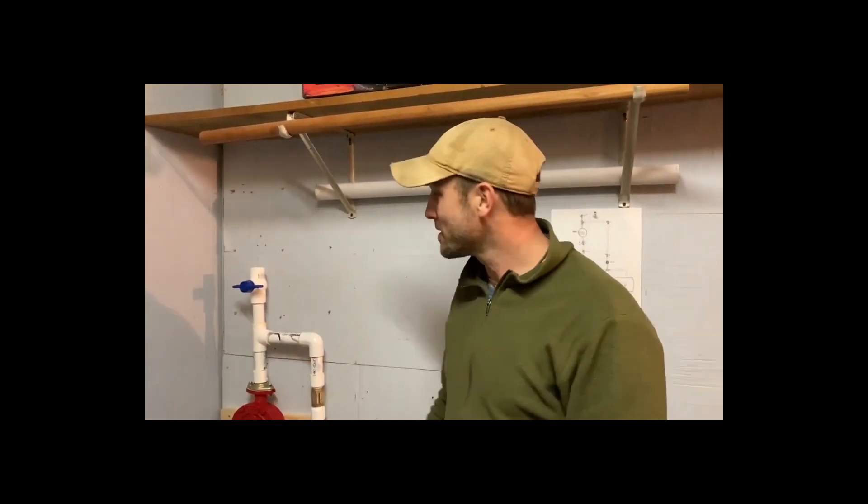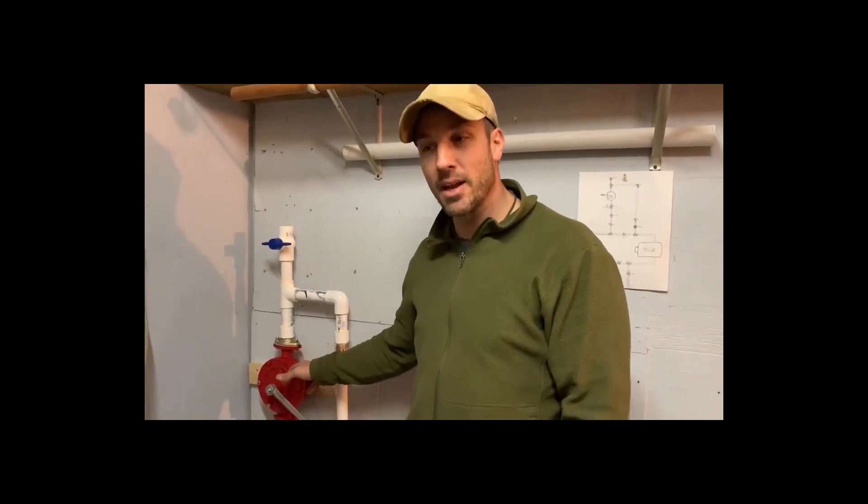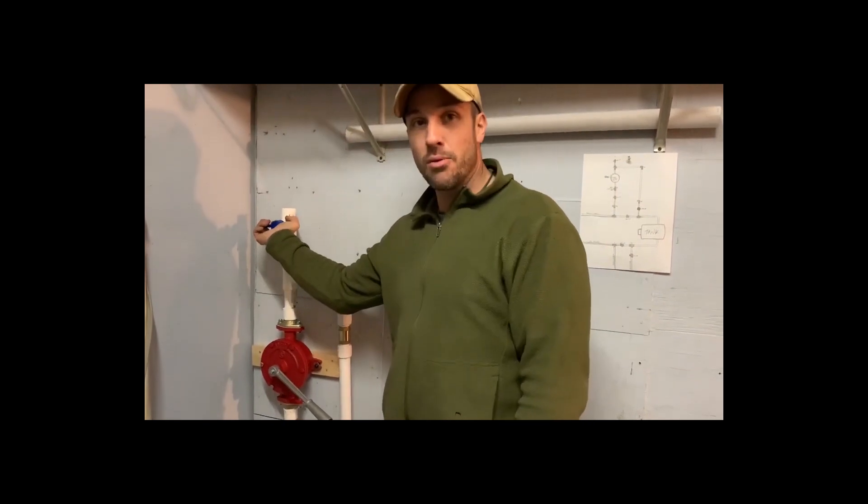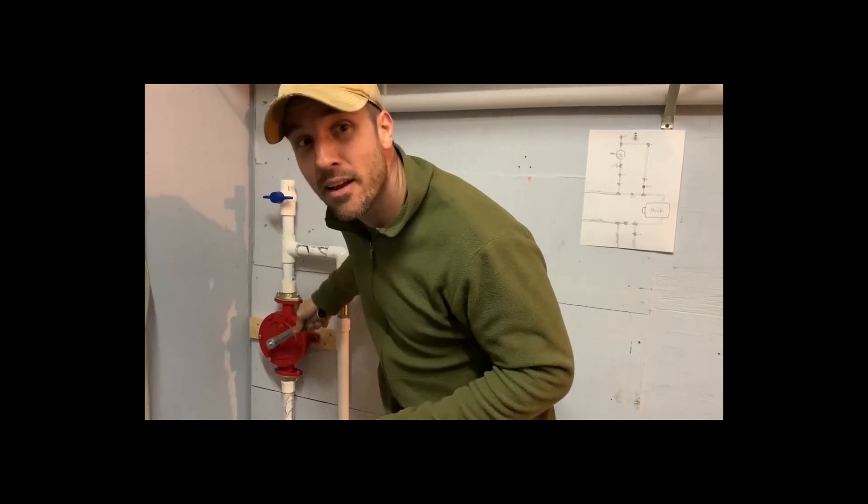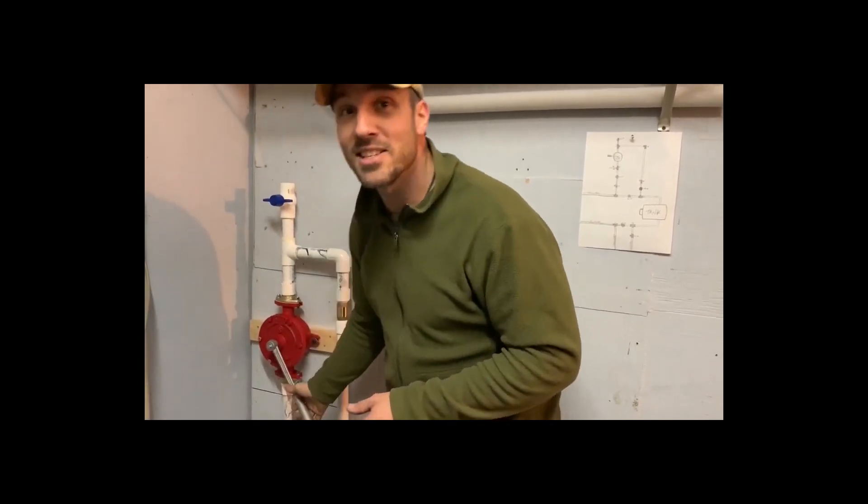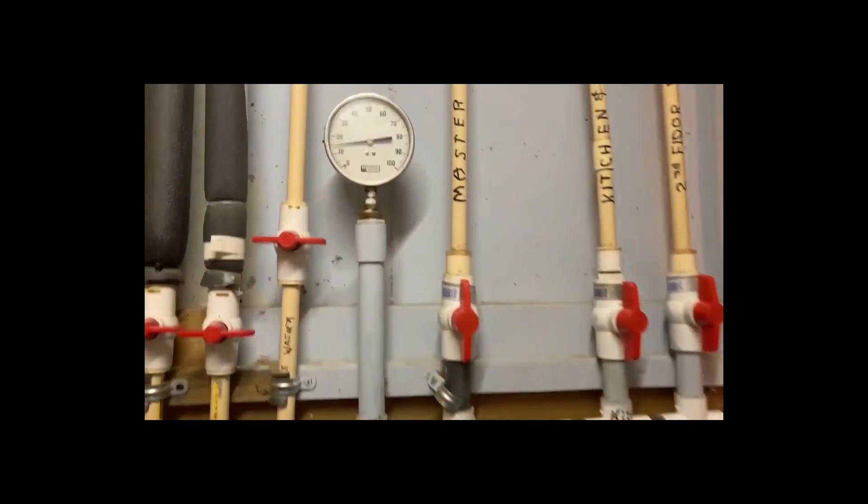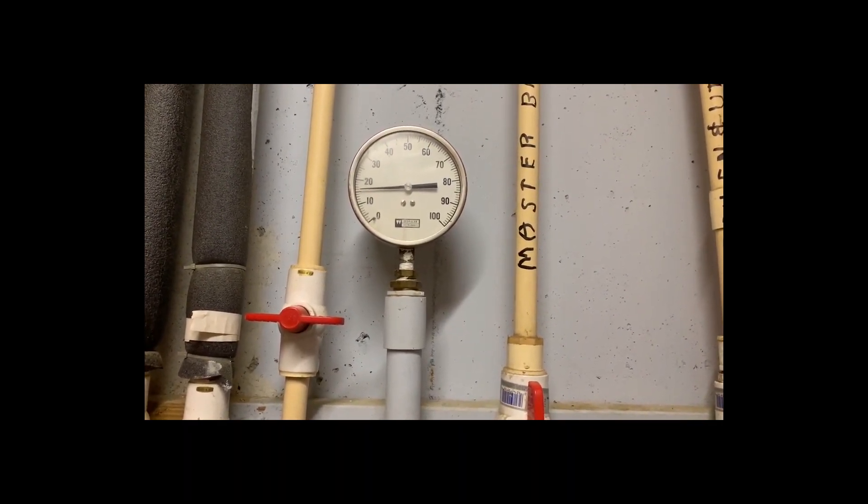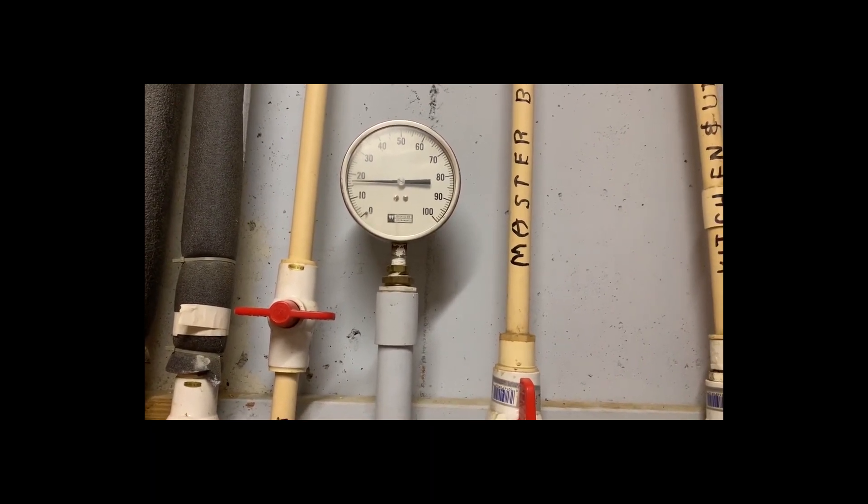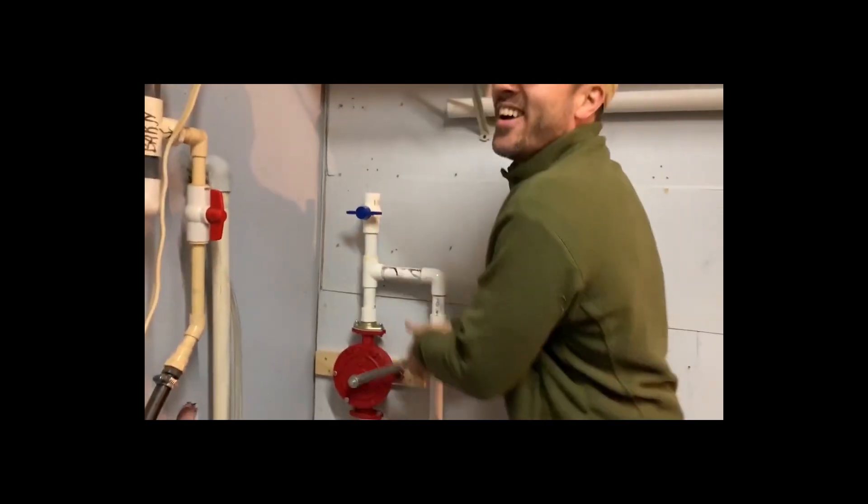So the pump wasn't working initially and I was bothered by it tremendously. I could not figure out what was going on, and then I thought to myself maybe there's no water actually in the pump yet and I didn't prime it. So I opened this up and let it breathe a little bit and it spurted out some air. And now listen—that's the sound of water flowing. Look at the pressure rising. With each pump I'm getting a couple PSI. Look at that!